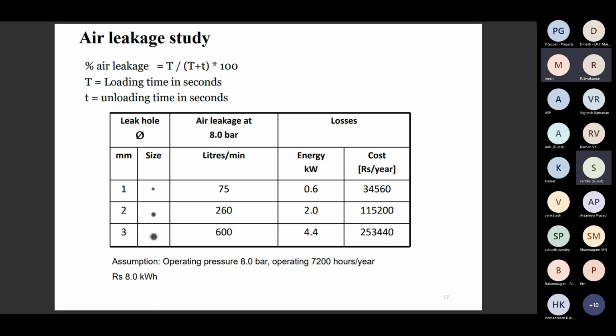Another thing is leakage. Leakage is present in all industries. Normally the recommended leakage should be below 5%, but practically it ends up at more than 20%. Some units have 30-40% also. So every leakage will be costly.